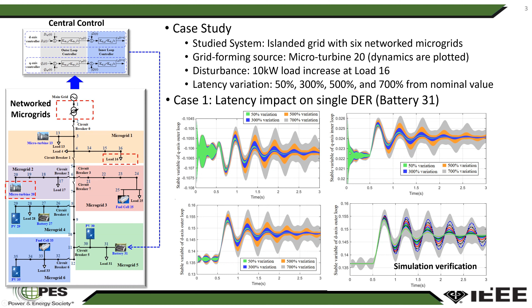And here is the second case. In this case, we consider multiple communication latencies on DER units, and more specifically, we look at the communication latency on battery 31 and fuel cell 33. And here is the simulation result. Different color zones show you different reachable sets. From this result, we can see there is a critical communication network latency. Within this latency, our system can maintain stable operations. But beyond this communication latency, most likely our system is going to lose stable operation. In this specific case, the critical operation point is 500% variation of the baseline communication latency.